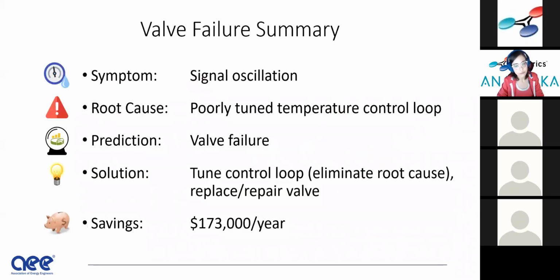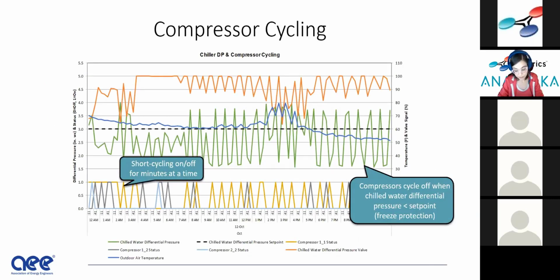By the way, the loop tuning, I won't go into it too much, but that's not necessarily straightforward, especially if there are issues with nonlinearity and things like that. So sometimes loop tuning can take 6 months, a year to get somebody in and really tune the loops properly. So it's not trivial. The next example is compressor cycling. I'll shoot through this pretty quickly because I think we're familiar with this sort of thing.